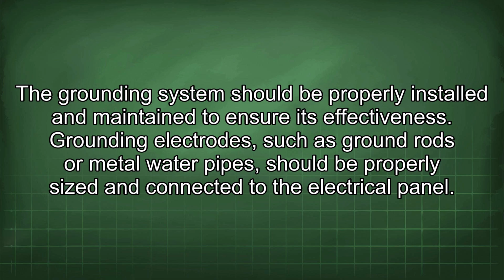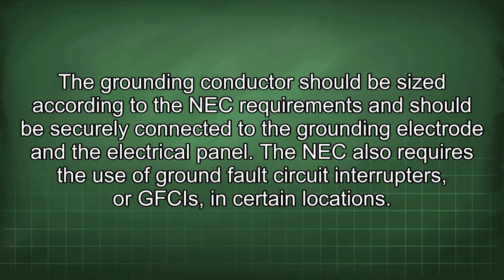Grounding electrodes, such as ground rods or metal water pipes, should be properly sized and connected to the electrical panel. The grounding conductor should be sized according to the NEC requirements and should be securely connected to the grounding electrode and the electrical panel. The NEC also requires the use of ground fault circuit interrupters, or GFCIs, in certain locations.